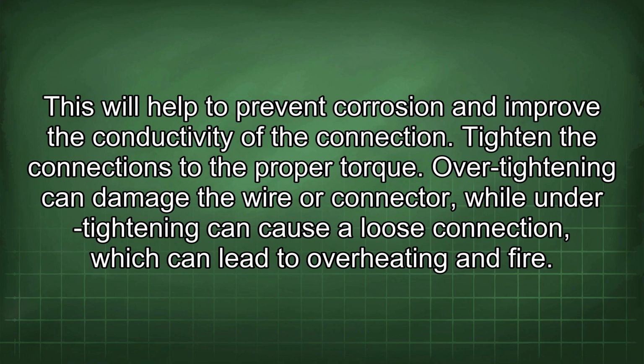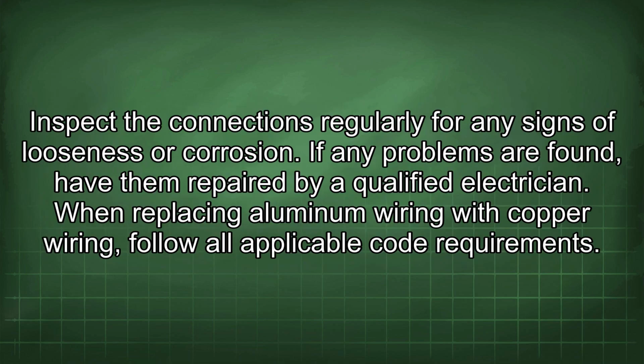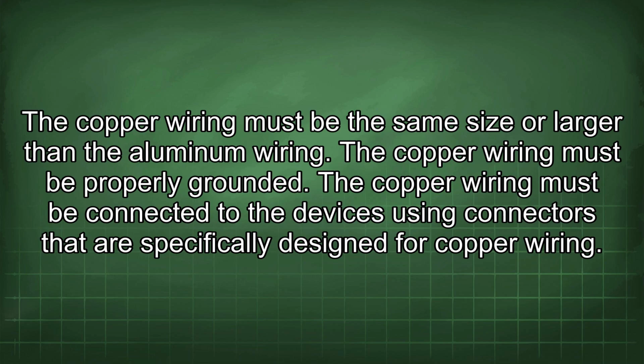Over-tightening can damage the wire or connector, while under-tightening can cause a loose connection, which can lead to overheating and fire. Inspect the connections regularly for any signs of looseness or corrosion. If any problems are found, have them repaired by a qualified electrician. When replacing aluminum wiring with copper wiring, follow all applicable code requirements. The copper wiring must be the same size or larger than the aluminum wiring. The copper wiring must be properly grounded. The copper wiring must be connected to the devices using connectors that are specifically designed for copper wiring.